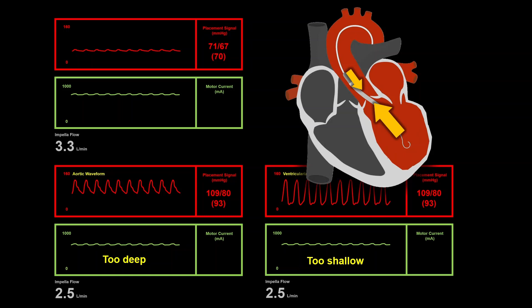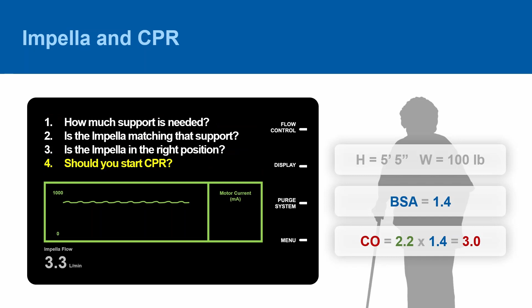We've now seen that for this smaller patient, 3 liters of cardiac output is needed to maintain a physiologic cardiac index, and that the Impella in this scenario is matching that level of support. We also saw that the Impella is in the right position and operating efficiently as indicated by the relatively flat aortic placement and motor current waveforms. Finally, we must ask ourselves if CPR is indicated in this setting.